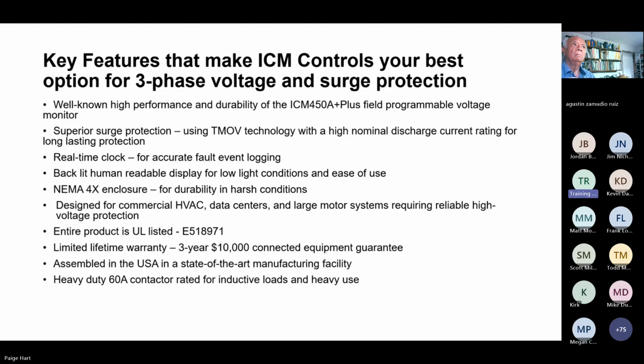Now, what does that mean for the customer? What that means is that UL hit this control 15 times in a row with 20,000 amps and it didn't fail. So that means this is a very durable product. It can take multiple hits within its range and not be damaged. Like any surge protection, over time, with many hits, eventually the surge protector will wear down. But this rating means that it will wear down slower. It will withstand a higher amount of abuse before it finally gives out.